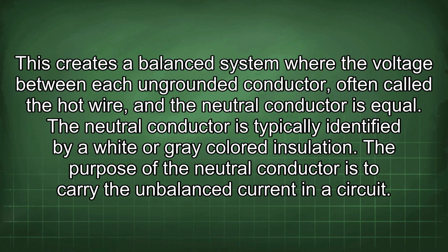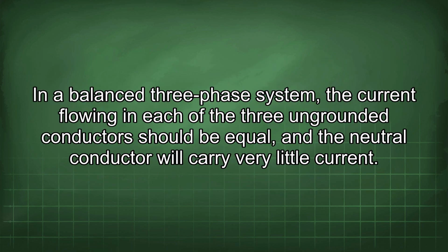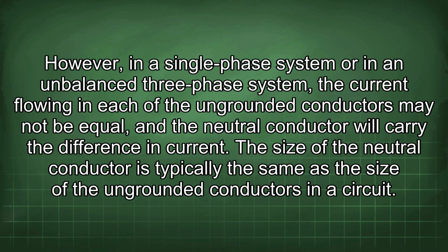The purpose of the neutral conductor is to carry the unbalanced current in a circuit. In a balanced three-phase system, the current flowing in each of the three ungrounded conductors should be equal, and the neutral conductor will carry very little current. However, in a single-phase system or in an unbalanced three-phase system, the current flowing in each of the ungrounded conductors may not be equal, and the neutral conductor will carry the difference in current.